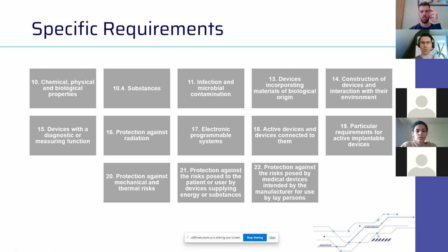Whether those sets of requirements apply to your product or not is of course based on the structure and technological characteristics of your product and foremost the intended purpose. Meaning if you don't want to emit ionizing radiation, you better not have an ionizing radiation button, because otherwise somebody would say, well, it's intended to emit ionizing radiation. So the intentional radiation would not be applicable. The unintentional radiation, you should have a look at.